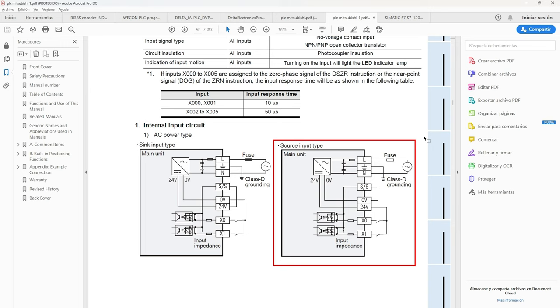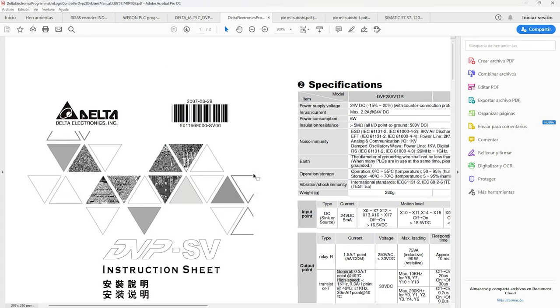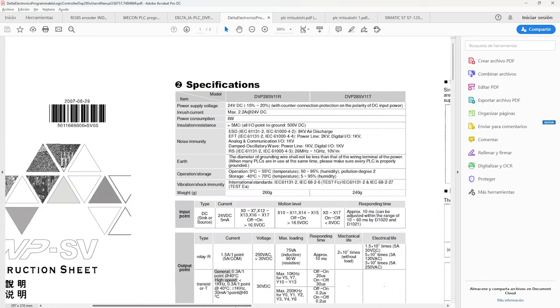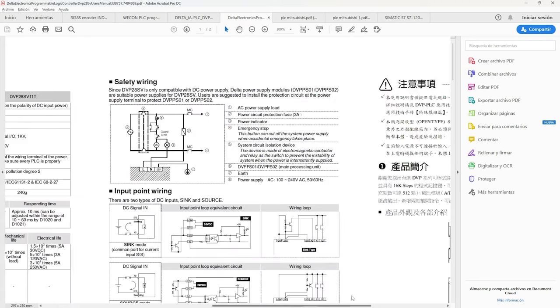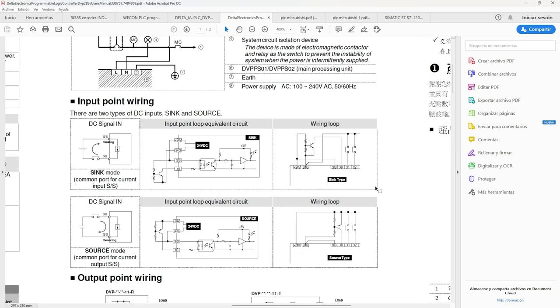It is the same case for the Delta PLC which according to its scheme, if the SS terminal is negative we will have an NPN input signal, and if it is positive it will be a PNP signal.